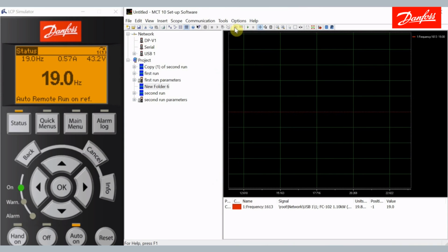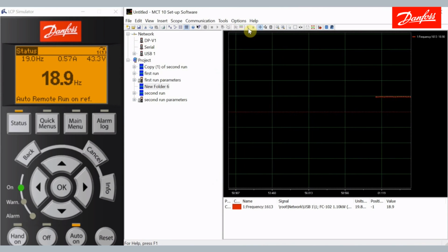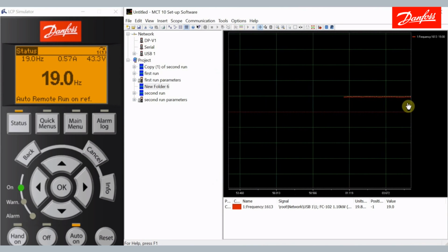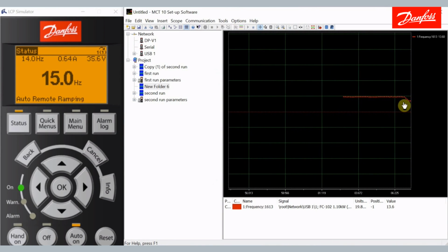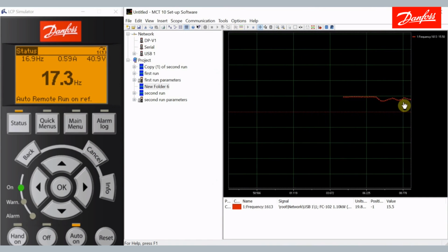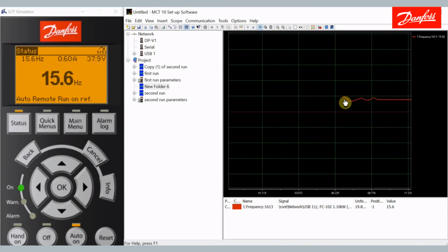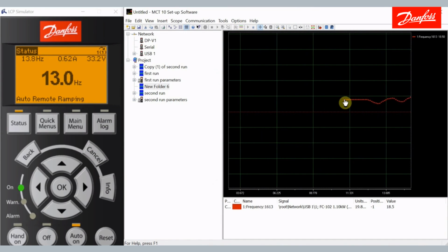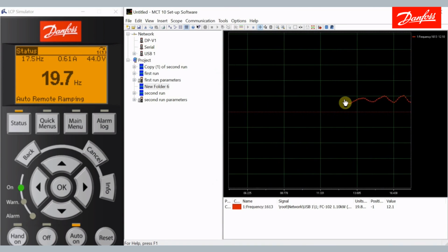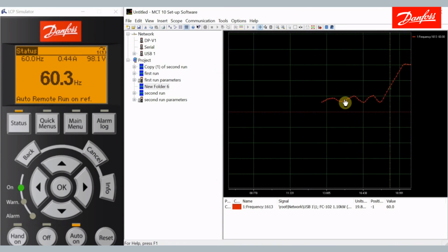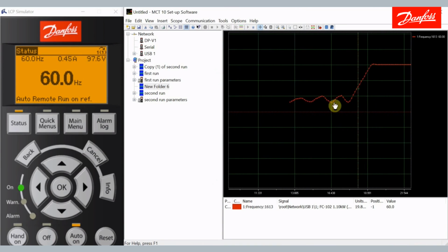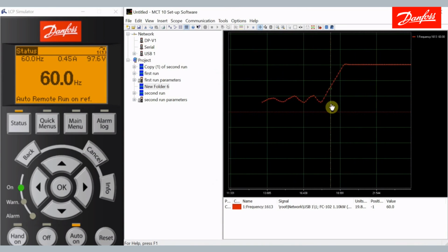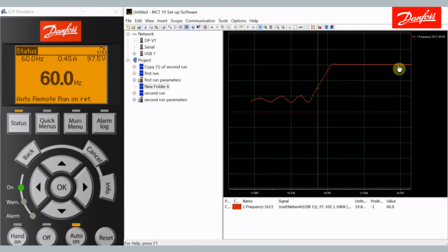If we start data acquisition, resume tracking, it's going to wind out here about 4 seconds. The buffer before the trigger is full. Still tracking, still acquiring data. The moment I hit 30 hertz, it triggers. It keeps whatever was happening the 4 seconds before the trigger. It collects 6 seconds after.